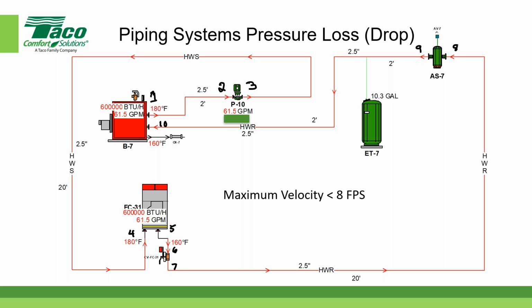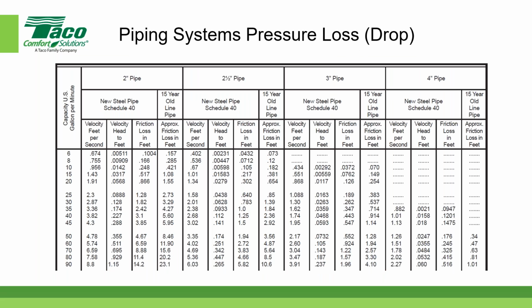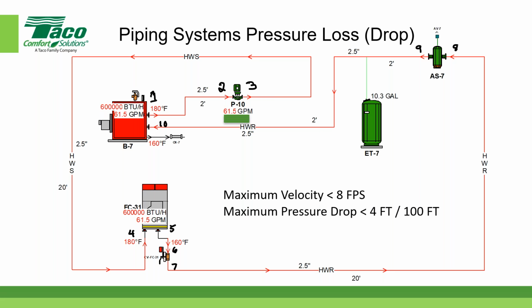So in our case, we have the maximum velocity. We want to remind everybody of our initial design criteria of 8 feet per second or less. We want to have a maximum pressure drop of 4 feet per 100 feet or less. So in our case, we have to decide first what the pipe is. So let's go back here. Let me erase these numbers. Well, I'll leave them on there for a moment.